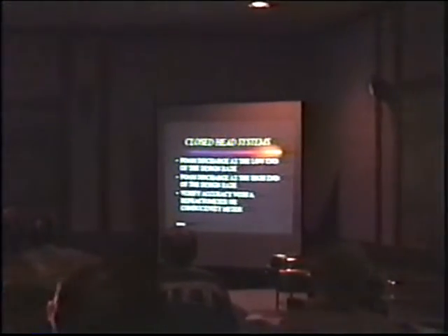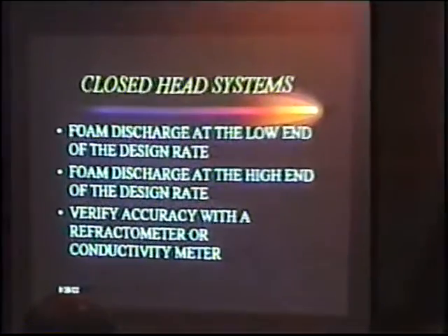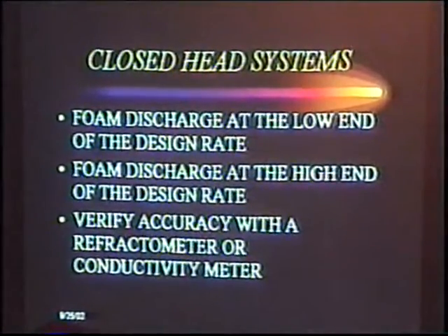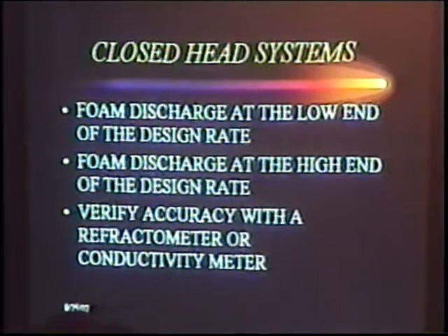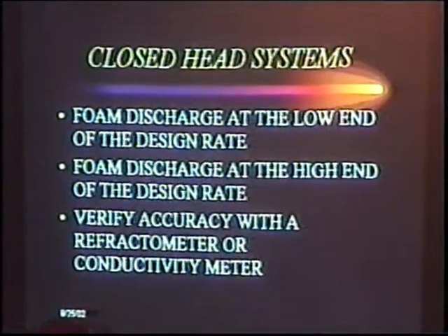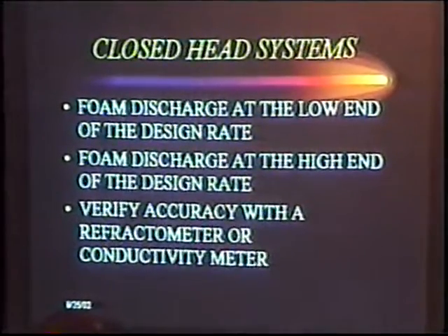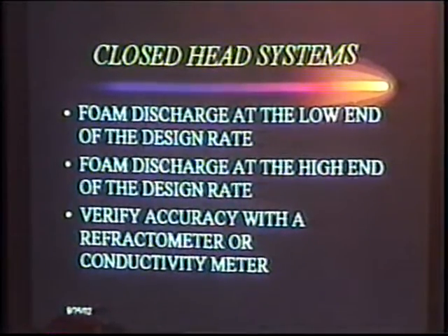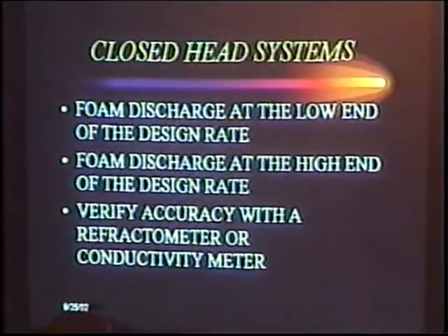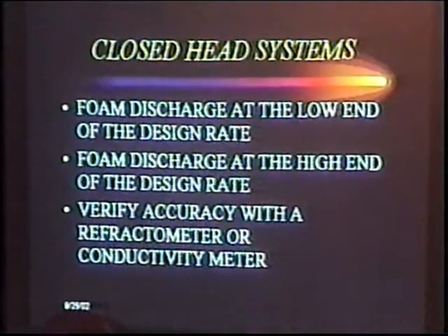Closed-head systems, obviously, you can't discharge the whole thing, so you usually have to set up some type of test valve pattern. You're going to test at the low end of your design, or the low end of the proportion, and then you typically run a test at the high end of the system design. A lot of times, when it gets up to the insurance carrier and the local authority, you all reach a compromise, especially since you've got to contain all this stuff in some measure, and just shoot maybe a mid-range flow, and shoot it into a containment pond, or directly into a truck, which will then haul it away. And occasionally, you run into a site where you just shoot it out the back parking lot.